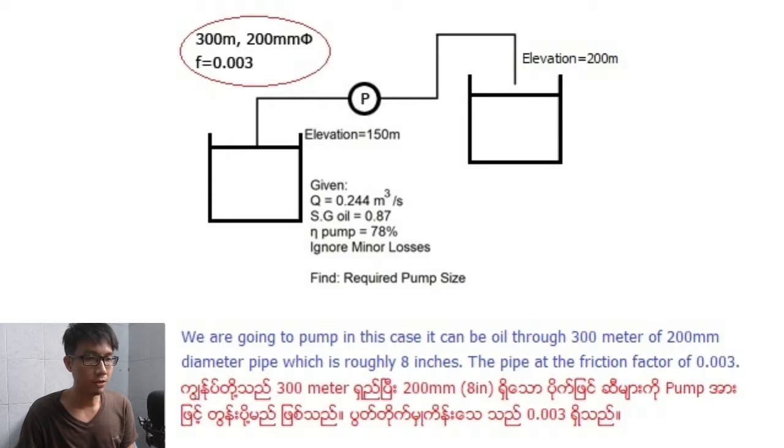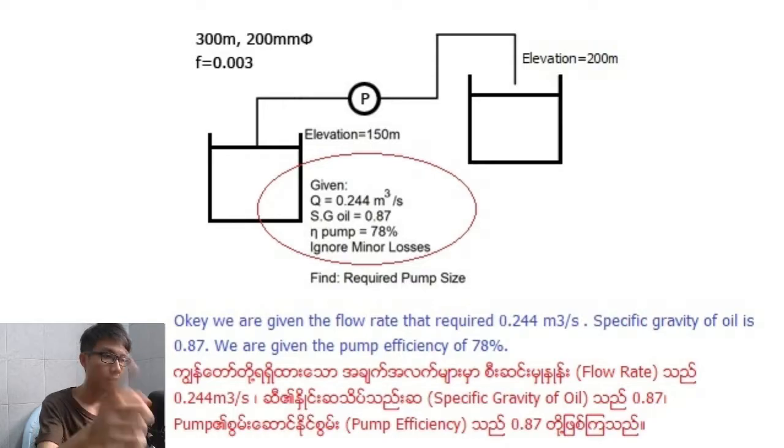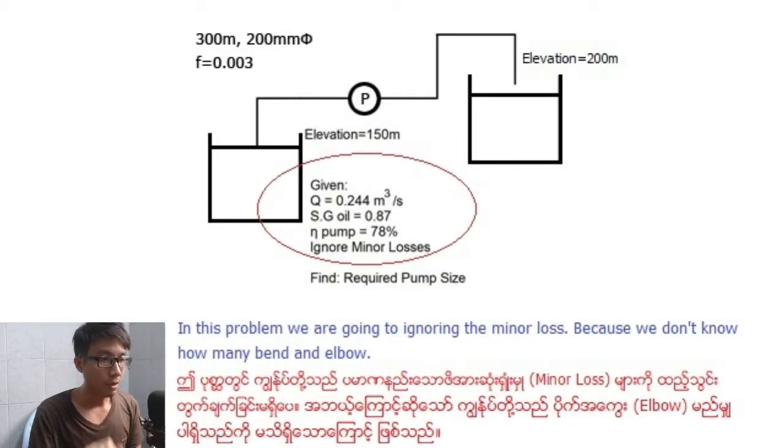The pipe has a friction factor of 0.003. We are pumping from a reservoir at 150 meter elevation to elevation of 200 meters where it will discharge from the pipe and go into the reservoir. We are given the flow rate required as 0.244 cubic meters per second. Specific gravity of the liquid is 0.87. We are given the pump efficiency of 78%. In this problem, we are going to ignore the minor losses because we don't know how many bends and valves.